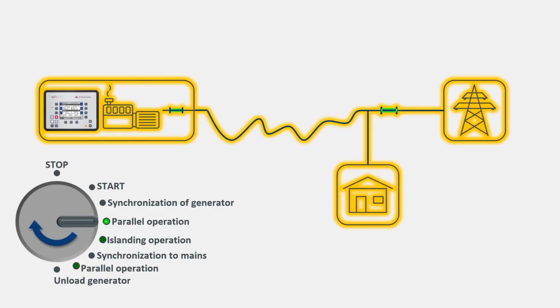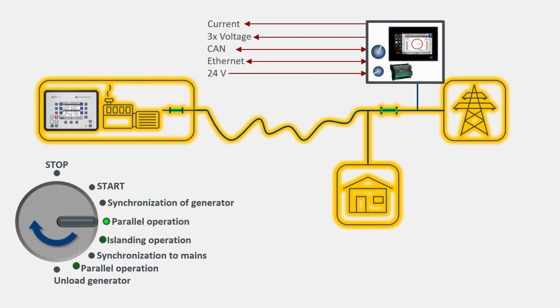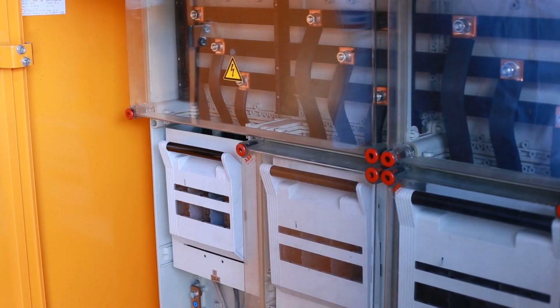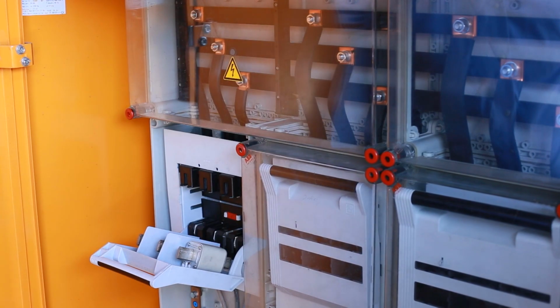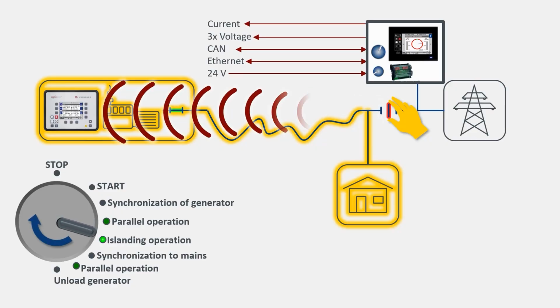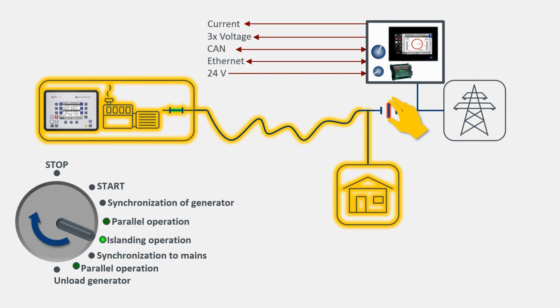We connect the EasyGen's grid sensing measurement before going to island operation. To safely disconnect from the utility, the EasyGen control can make sure that the mains breaker or the manually operated load breakers, like fuses, will be opened when the power flow is close to zero to avoid electric arcs. Once the mains breaker or fuses are opened, the EasyGen will automatically detect it via phase angle sensing, and it will automatically switch the operation mode from mains parallel to island mode. There is no need for a mains breaker feedback or a breaker release signal. This makes the operation for the technician easier and foolproof.